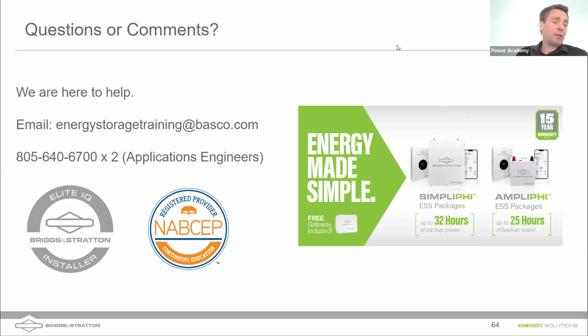There are a lot of considerations that go into how quickly you charge and discharge batteries. Depth of discharge is also quite important. If you are discharging daily or multiple times a day, we recommend you don't go below 20% state of charge, meaning discharge your battery but leave 20% in at the bottom. So you're using 80% of the available capacity. That does mean you'll need maybe an extra battery. If you have a 5 battery system, cycling to only 80% depth of discharge is equivalent to 4 batteries, so there's an added cost, but we're expecting more than double the number of cycles compared to 100% depth of discharge. I'd recommend not going below 20% state of charge. We don't see a big increase in cycle life from shallower cycles than that; going down to just 50% would probably not increase the value of that system.